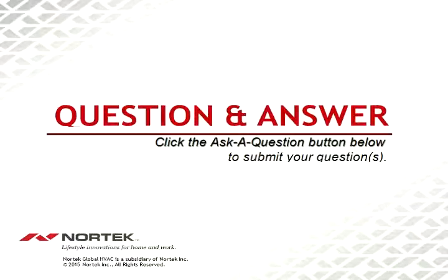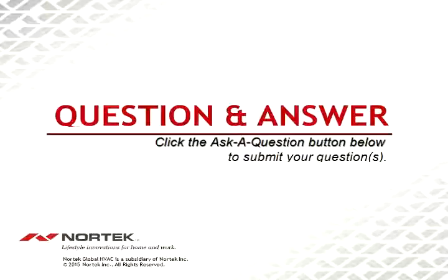That was one good question. Let's see what else we got here. If a stuck reversing valve is freed up, will it stick again? Yeah, if you get one freed up, it might get you by for a little while, but it's probably going to stick again. Keep submitting your questions. Got some good questions coming in.